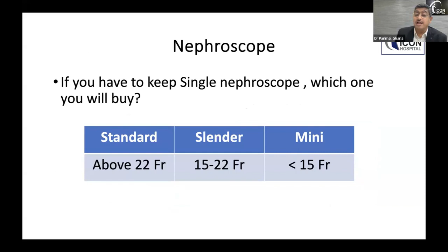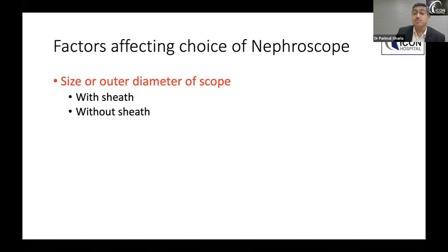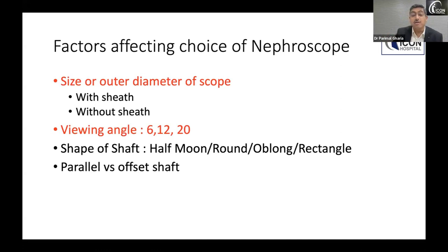So what are the factors which can affect the choice of your nephroscope? The size or diameter of the scope, depending on what dilatation you want, decides the choice of your nephroscope. Viewing angle: some nephroscopes have a typical viewing angle which is comfortable for some and not comfortable for others, so you need to decide which angle of view you want to use. Then there are some scopes which are half moon, round, oblong or rectangle, the different shapes of the sheath or shaft. Then you need to check whether it is parallel or offset.